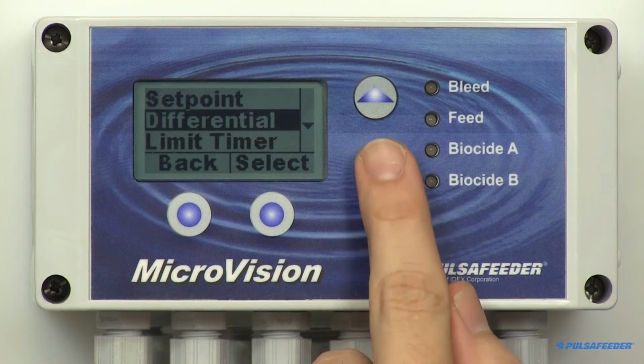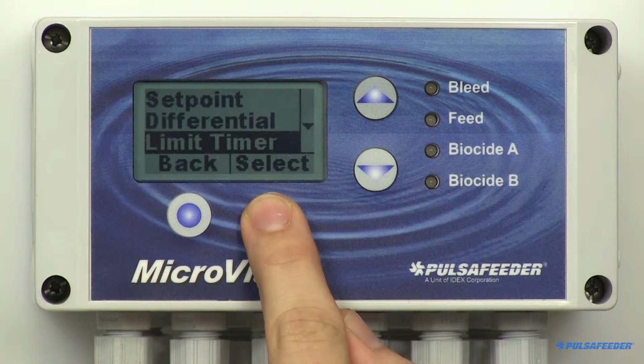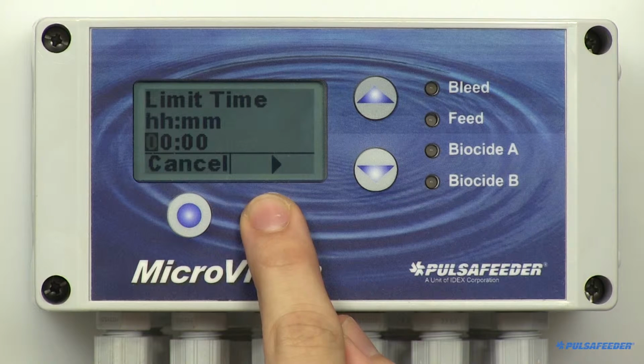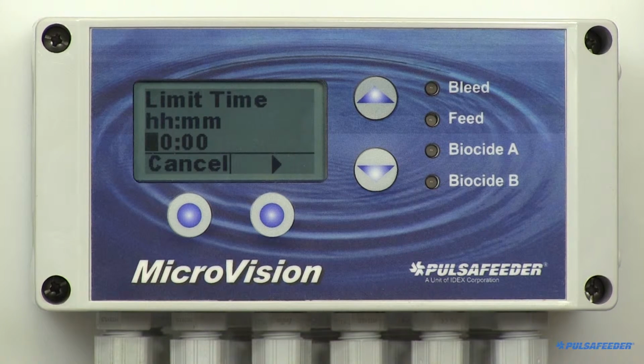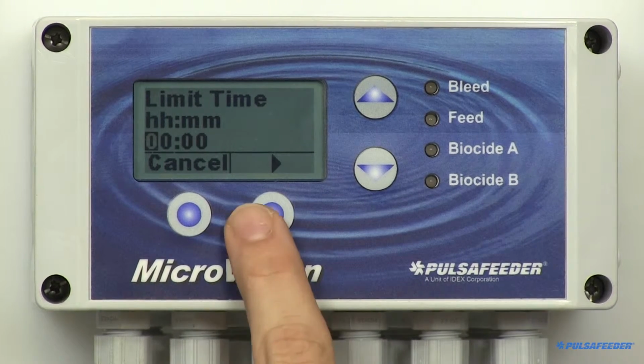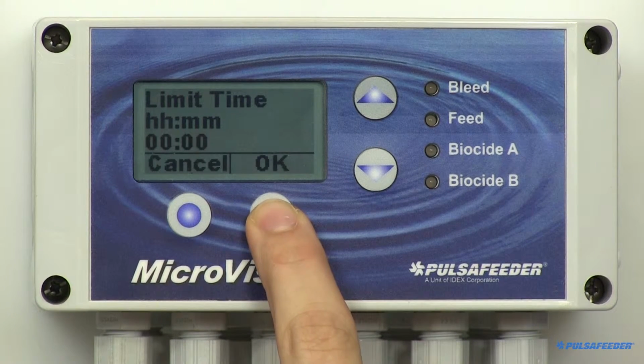The bleed relay has a limit timer so you can set the maximum amount of time the bleed output can stay energized before a bleed limit alarm is reported. The limit timer, when exceeded, only reports an alarm. It does not turn off the bleed relay. If the next bleed cycle completes without alarm, the alarm will clear itself. Use the arrow buttons to enter hour and minute values. Setting the value to zeros disables the timer function. Then hit Enter and OK.